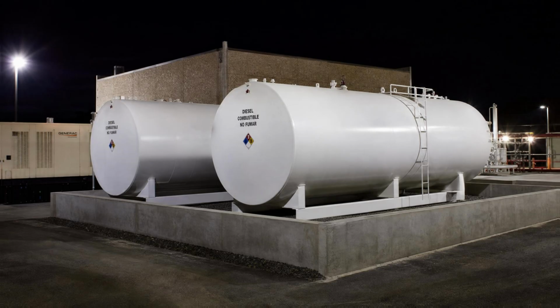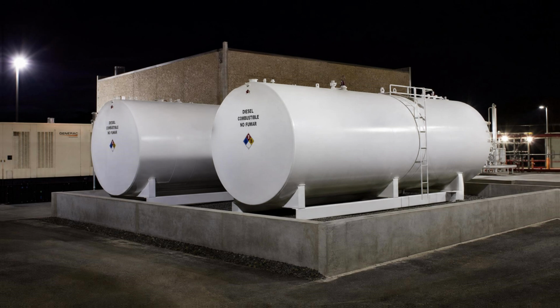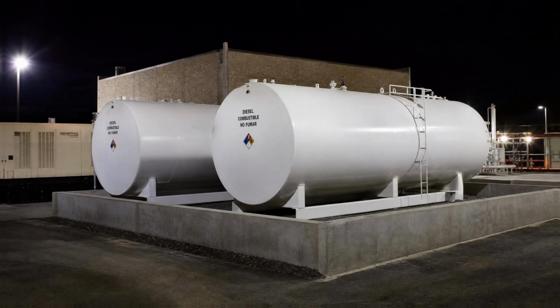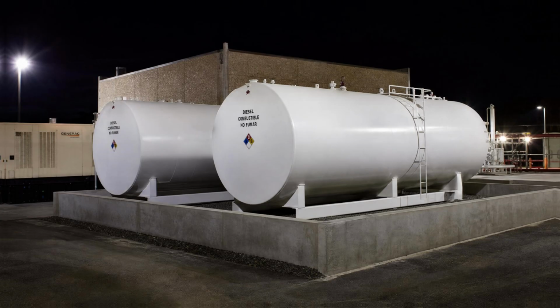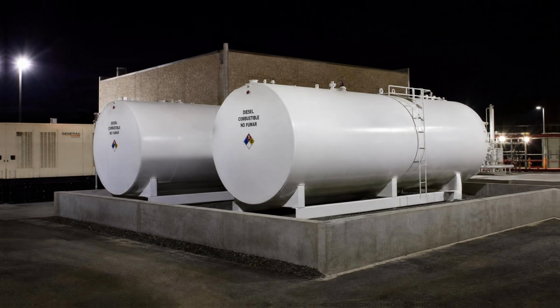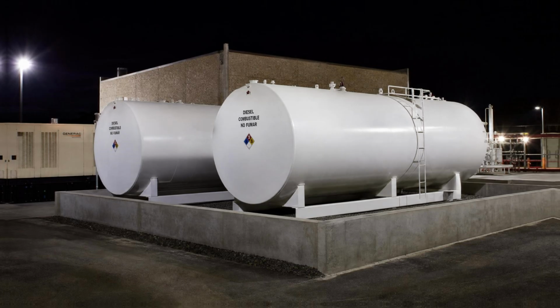Because the hospital's emergency power system must continue to function even if something goes wrong with one of the backup sources themselves. The single point of failure that is acceptable in a less critical building is not acceptable here. If one generator fails to start, another must be ready to take over. If one transfer switch develops a fault, the loads it serves must have an alternate path to power. Redundancy is layered into the hospital's emergency power design in a way that reflects the seriousness of what the system is protecting.